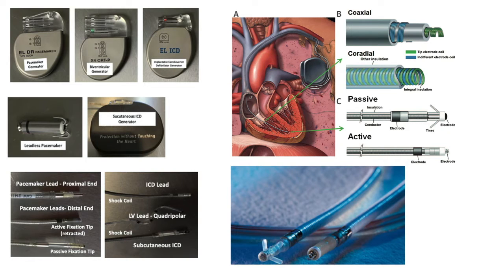These porous tips increase the contact with the electrolytes, reduce the polarization voltage, and promote rapid tissue ingrowth. The tip of the leads is attached to the myocardium either by a penetrating helix, which is the active fixation, or by small tines or flanges that embed into the myocardial trabeculations, which is the passive fixation method. At the proximal end of the lead is the connector, and this connector pin is fixed by a screw mechanism to the pacemaker generator at the time of pacemaker implantation.